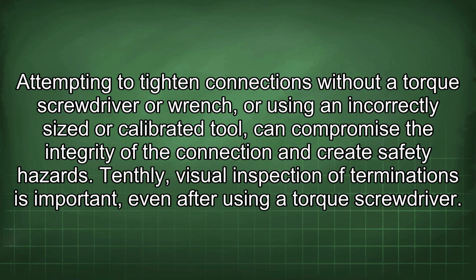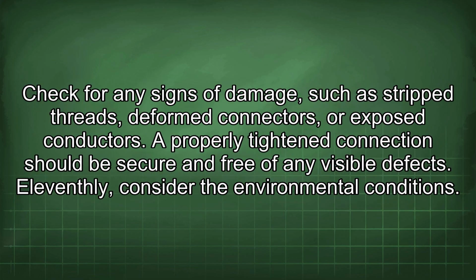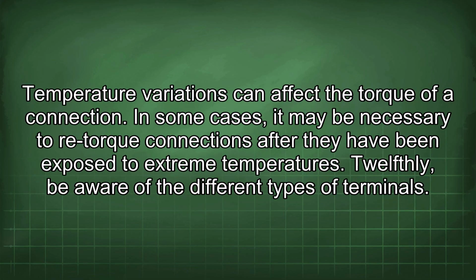Tenthly, visual inspection of terminations is important even after using a torque screwdriver. Check for any signs of damage such as stripped threads, deformed connectors, or exposed conductors. A properly tightened connection should be secure and free of any visible defects. Eleventhly, consider the environmental conditions. Temperature variations can affect the torque of a connection. In some cases, it may be necessary to re-torque connections after they have been exposed to extreme temperatures.